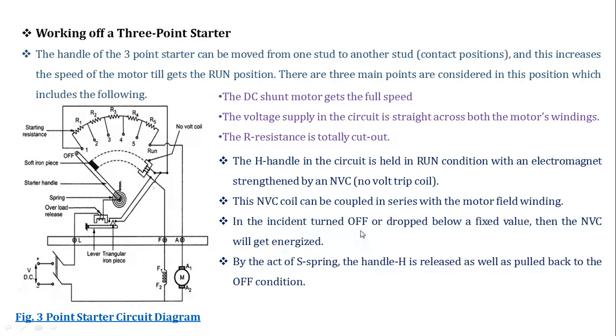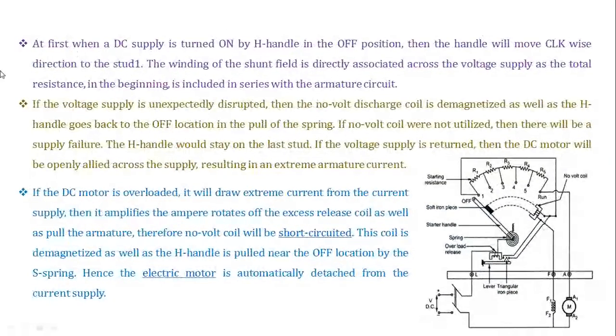If the supply is turned off or drops below a fixed value, then the NVC gets de-energized, and by the action of the spring S, the handle is released and pulled back to its off position. At first, when the DC supply is turned on and the handle is moved from the off position, the handle will move clockwise to stud 1, then stud 2, then towards stud 3. The winding of the shunt field is directly connected across the voltage supply, while the total resistance is included in series with the armature circuit at the beginning.